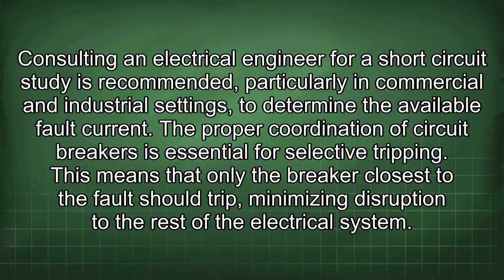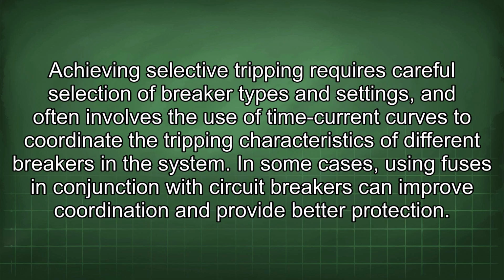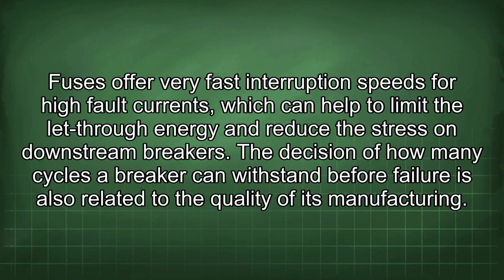The proper coordination of circuit breakers is essential for selective tripping. This means that only the breaker closest to the fault should trip, minimizing disruption to the rest of the electrical system. Achieving selective tripping requires careful selection of breaker types and settings, and often involves the use of time current curves to coordinate the tripping characteristics of different breakers in the system. In some cases, using fuses in conjunction with circuit breakers can improve coordination and provide better protection. Fuses offer very fast interruption speeds for high fault currents, which can help to limit the let-through energy and reduce the stress on downstream breakers.